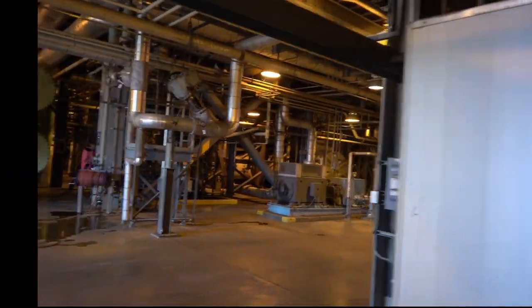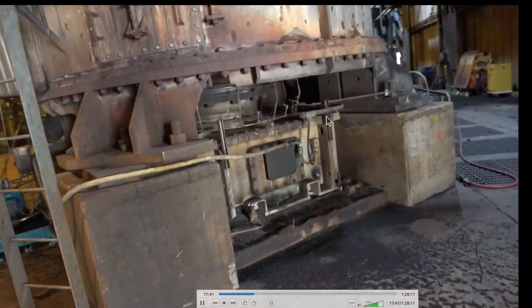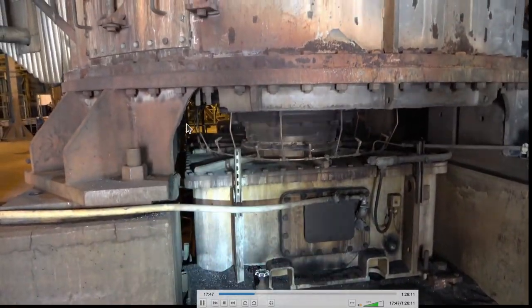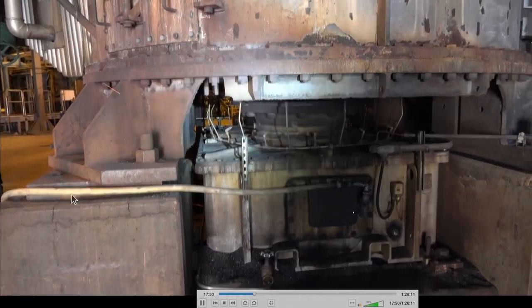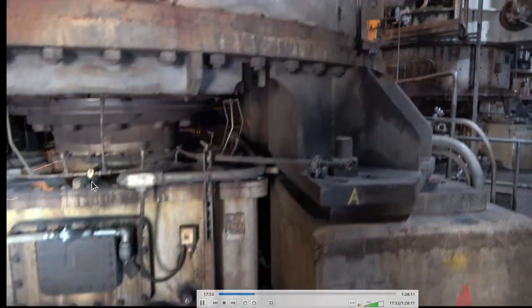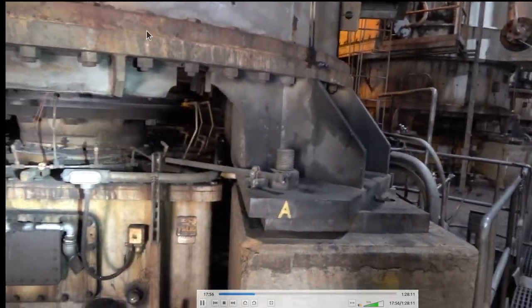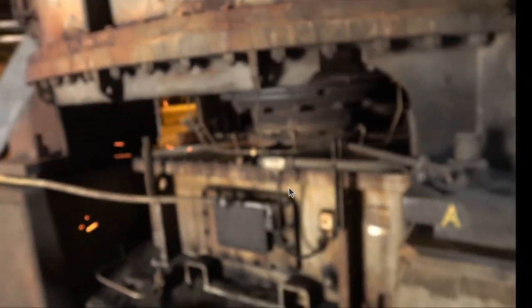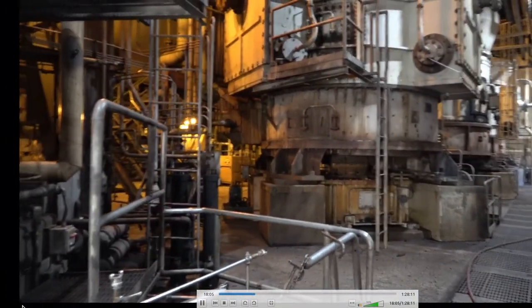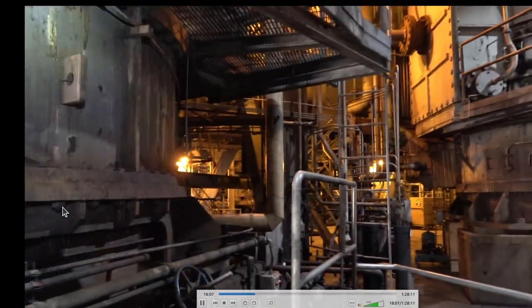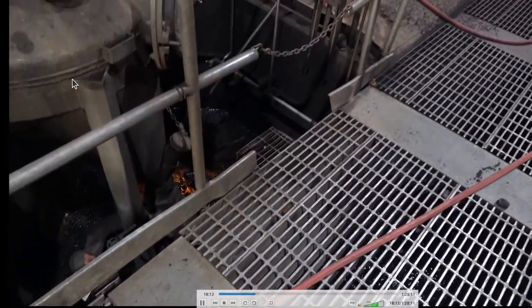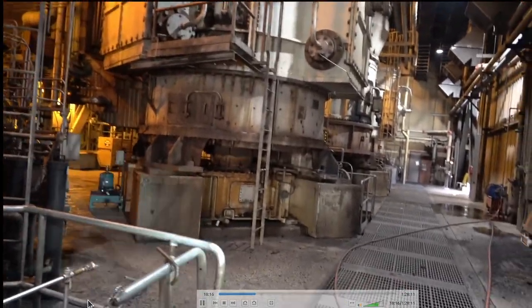Here are the heat exchangers for the aux cooling water. This is a pulverizer running — you can see the scrapers on it and about how fast they go. There's a gearbox down here, and three large wheels inside that roll — they're fixed, the table turns, and coal drops down and gets crushed. You've got a pyrite hopper on the side. Anything that accumulates and doesn't get ground, the scrapers kick out and drop down, then you sluice that out. Anything — rock or debris — ends up down here and you can sluice it out to a tank.